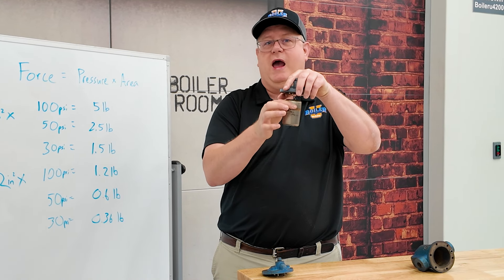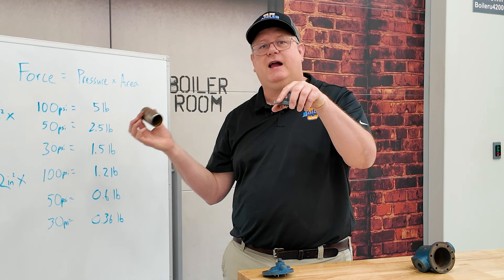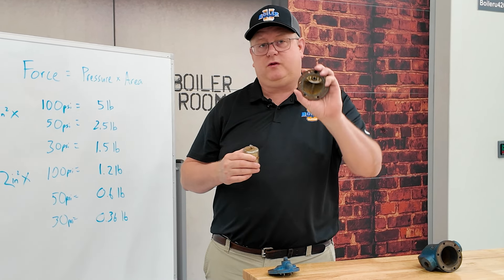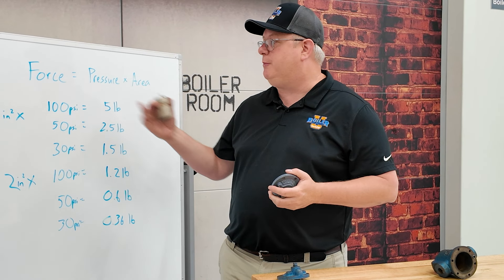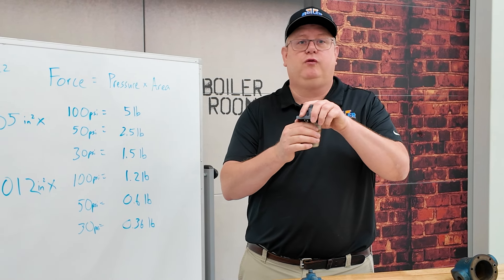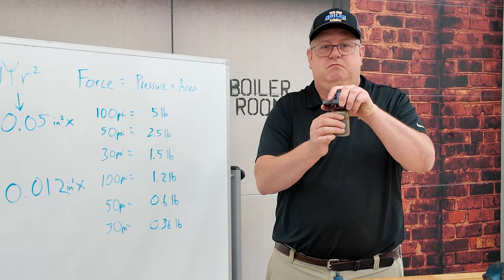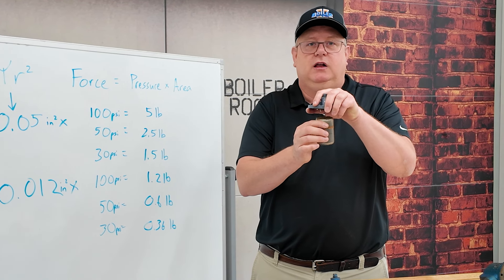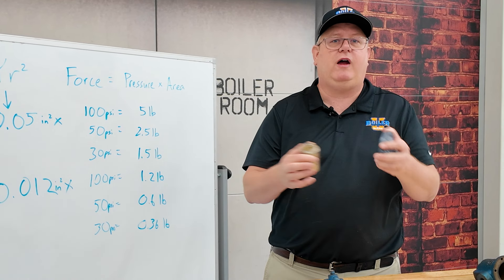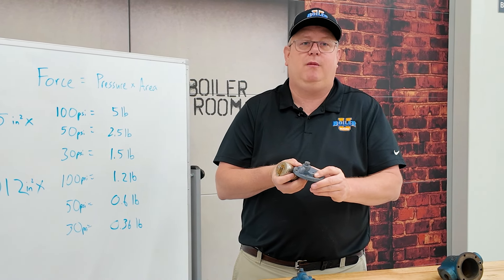With a little bucket, I have only the weight and a small amount of leverage to counteract that five pounds. So if I put this quarter inch trap on a high pressure application, it's going to close once, and until pressure is relieved from it, it's just never going to open again. A trap that you install may appear to fail closed right out of the gate — it may mean it's got the wrong PMO.